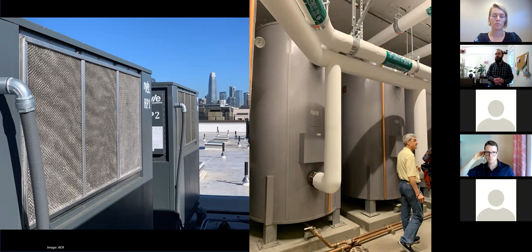Some considerations for heat pump hot water heaters: they're typically large amperage units or three-phase equipment, so you need adequate electrical capacity. You need to think about the distance from the closest panel on scattered sites—if you have a property with multiple buildings or a campus, you need to think about where you'll pull power from. And then transformers: you're potentially adding new load to the building if it's existing, so we need to engage early with the utility to make sure no transformer upgrades are required or triggered by the added loads.